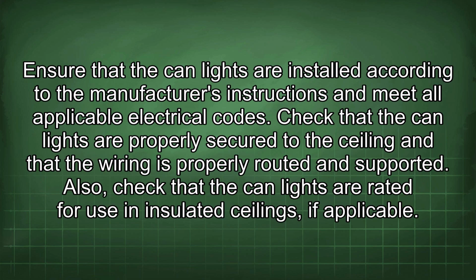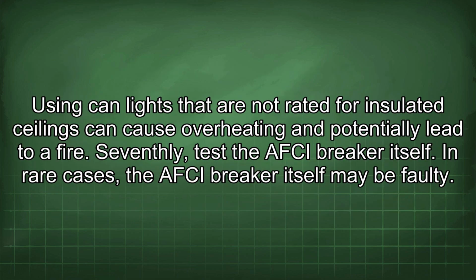Ensure that the can lights are installed according to the manufacturer's instructions and meet all applicable electrical codes. Check that the can lights are properly secured to the ceiling and that the wiring is properly routed and supported. Also, check that the can lights are rated for use in insulated ceilings, if applicable. Using can lights that are not rated for insulated ceilings can cause overheating and potentially lead to a fire.